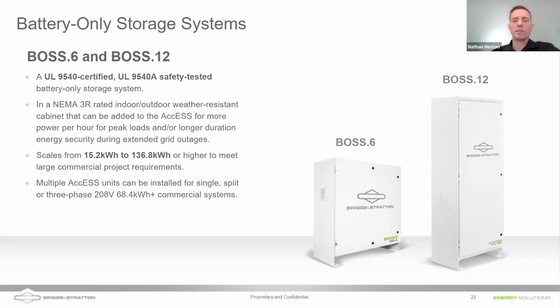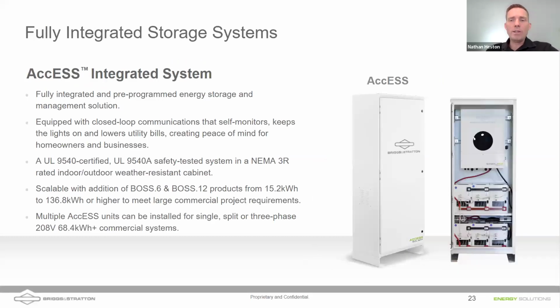One of the nice things is all the wiring and the components, the combiners, etc., are already inside these cabinets. We can use the Boss 12 cabinet as an AccESS cabinet and essentially have 6 batteries inside it. This is a popular option for both our inverter and the Sol-Ark 12k inverter, or even the 8k inverter. You can put them inside these outdoor enclosures and have a pretty close to plug-and-play solution that's UL 9540 certified, etc.